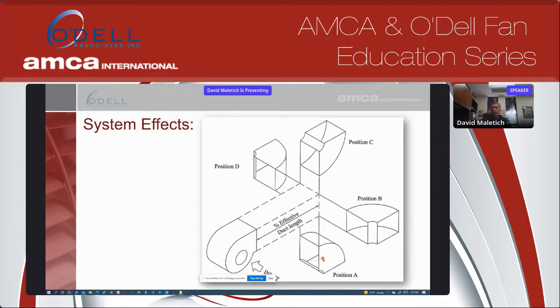Now, if you have to have an elbow, it's much better to have this position A elbow at the bottom here than a position C elbow. Again, air hugs the outside of the volute shape, comes up here, and if you have that position A elbow, it continues along the outside of the elbow, and then you can put your straight run duct here and get your regain at this point. If you have a position C elbow, air hugs the outside of the volute shape, hits the back of the elbow, has to get reaccelerated out of this duct, and you're going to have a fairly significant loss there.